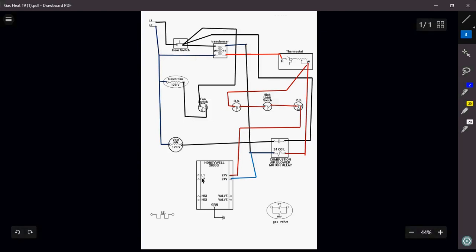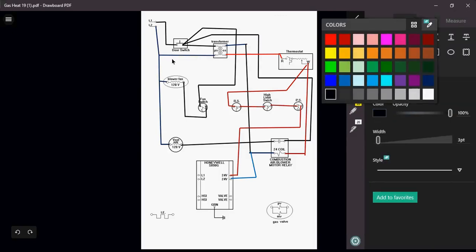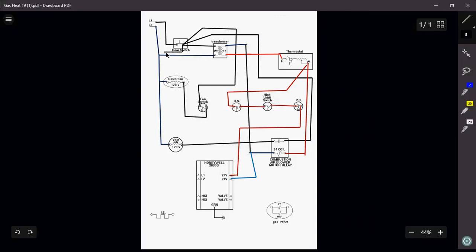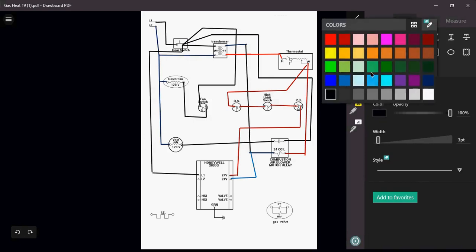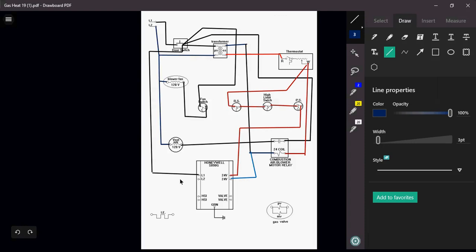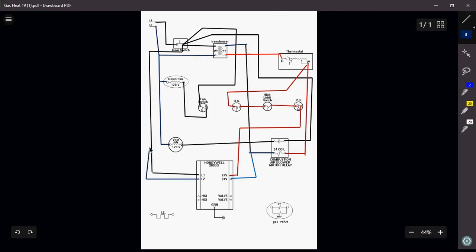Okay? I'm also going to have to send 120 volts down to my ignition module. The reason why this particular type of ignition module has an L1, L2 down here is because my hot surface igniter needs 120 volts in order for it to operate. So I'm going to send 120 volts. Okay? I'm going to send it right out of my door switch. And I'm going to come down right into my L1. My L2 is I'm just going to send it right back to my L2. Coming up. Let's go right back.